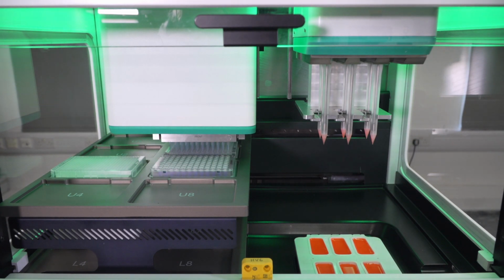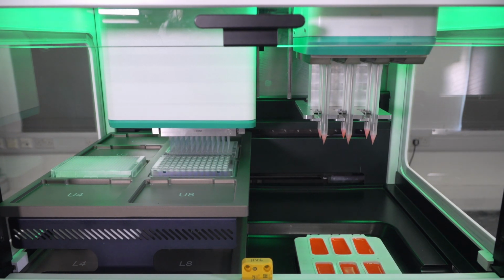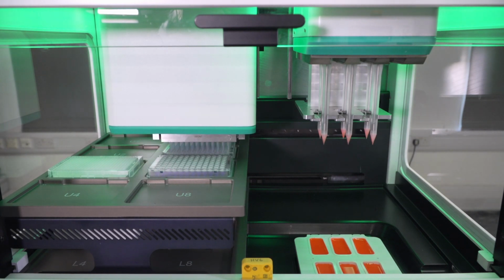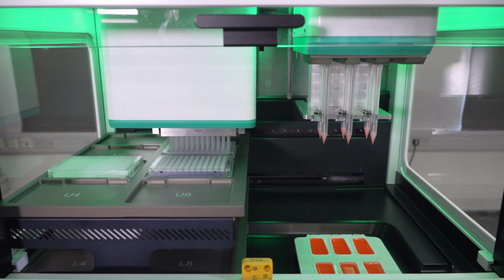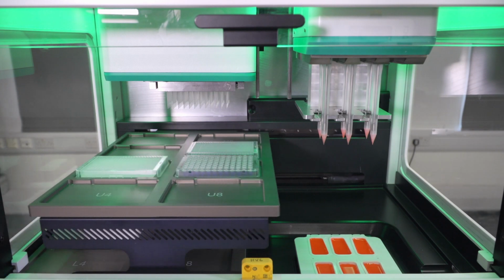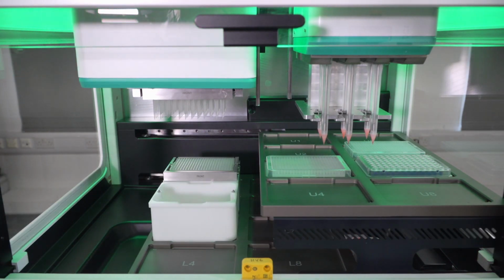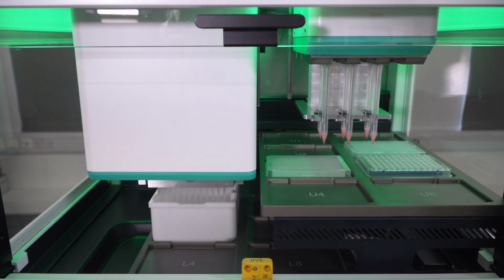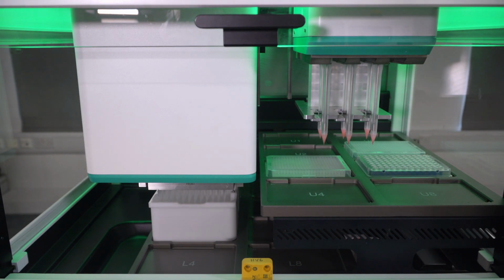And we can do that in a number of ways. We can touch off on the side of the wells, we can touch off at the liquid surface. It's all controllable within the protocol. So it's just moving to the final quadrant there. Again, just doing its final touch off. And now it's going to switch the tips out and pick up a set of 384 tips that it's going to use a little later in this protocol.